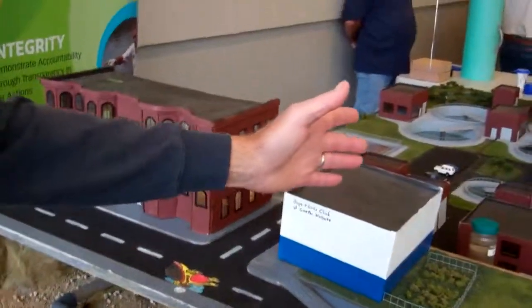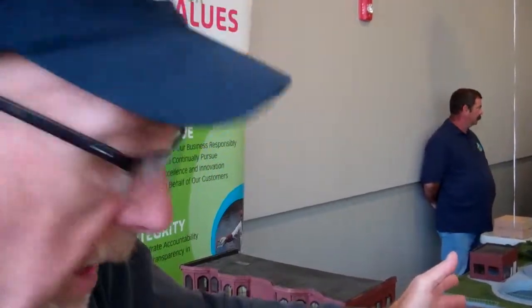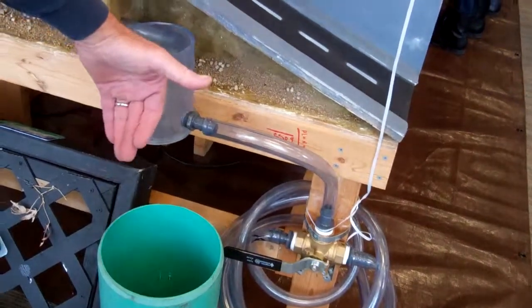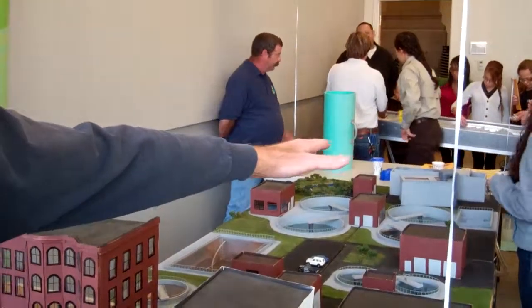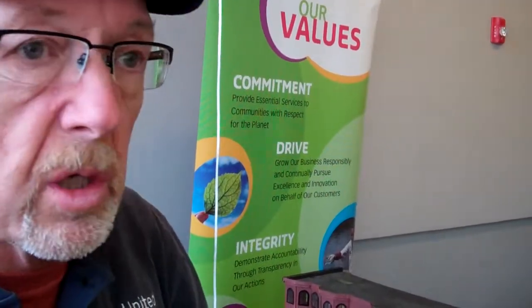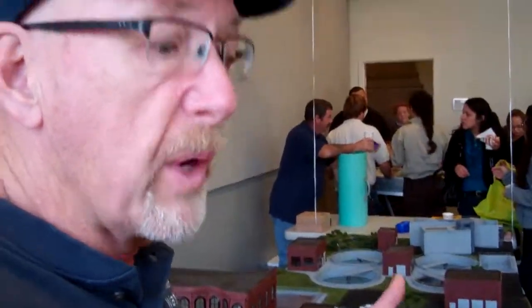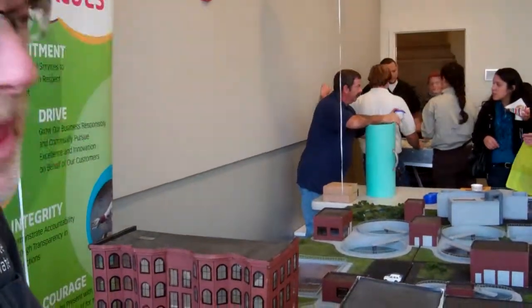So in Holyoke, the largest CSO, number 9, was built to capture that water and treat it. So we can simulate a CSO rain outfall, and then by opening the valve to the CSO facility, we divert the polluted water that would be going to the river to the CSO facility on the far end of the model. And it captures the water there, just like we do at the plant down the hill here. We screen out the coarse material, we chlorinate it, and then we dechlorinate it really quick before it goes to the river. So we test for E. coli. We have a permit, and we want to make sure our E. coli is below a certain number. So that water, which would go to the river prior, is no longer raw wastewater. It's treated water. So they get to actually do that here on the model.